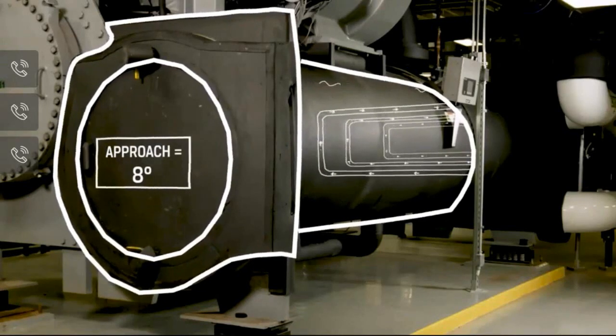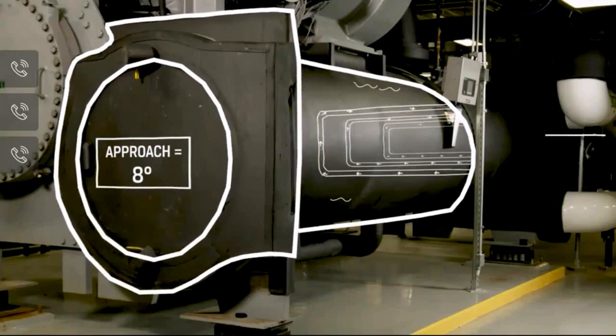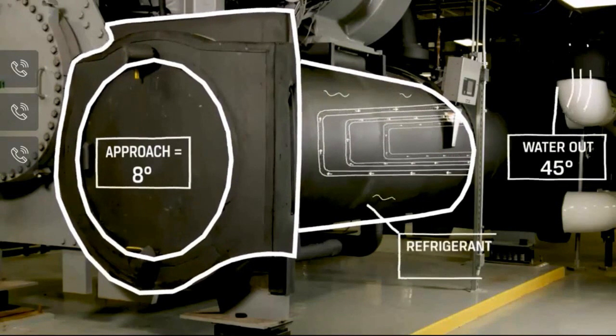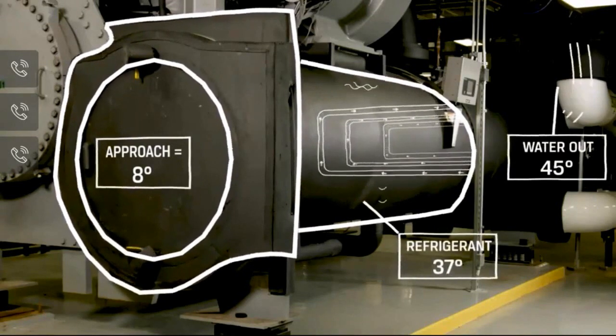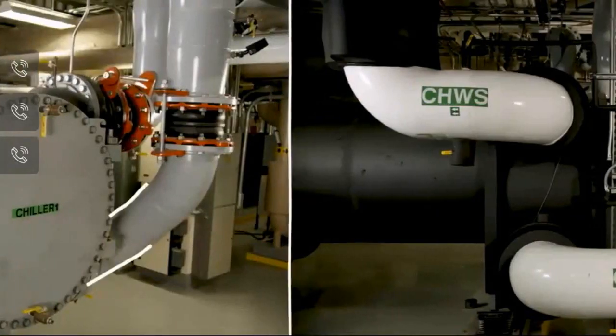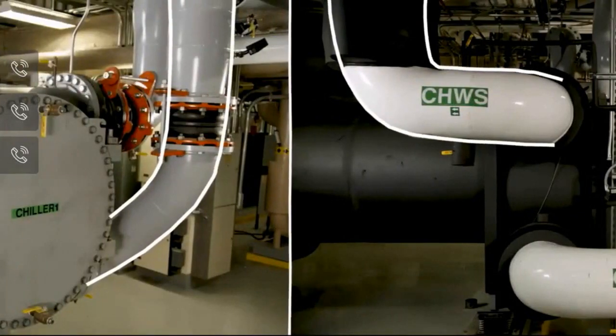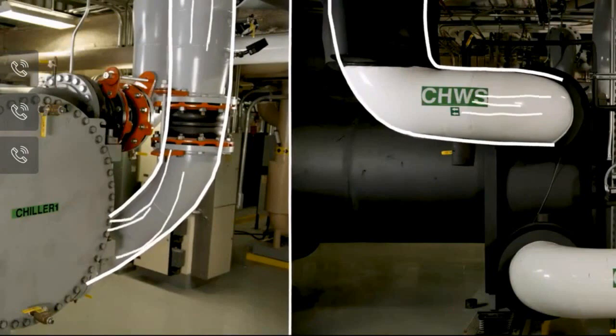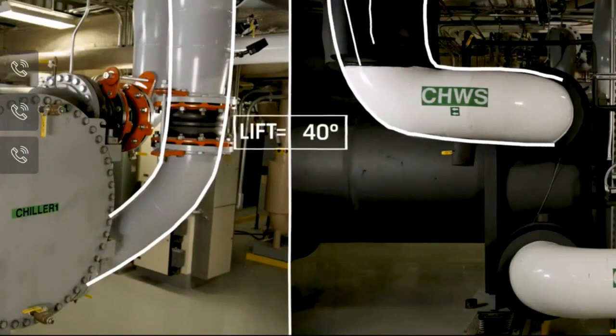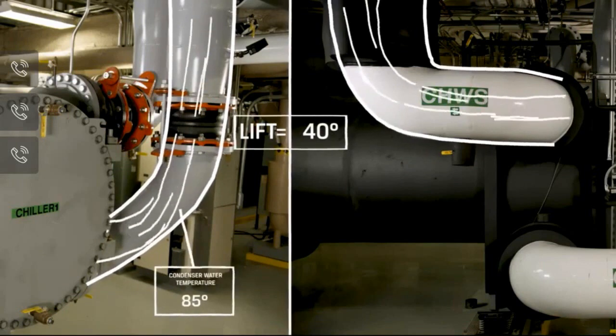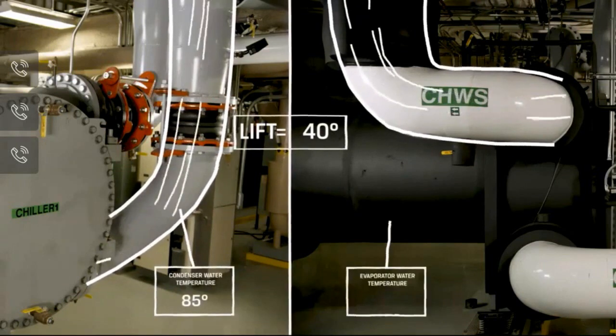In both cases, lower is better. A 1-degree difference in approach temperature represents a 2% decrease in efficiency. Low approach temperatures are a sign of good heat flow between the water and refrigerant. The third area of efficiency issues happens when balancing the cooling tower fan speed and chiller operation as characterized by chiller lift or head pressure. Chiller lift is the difference between the entering condensing water and leaving evaporator water temperatures.